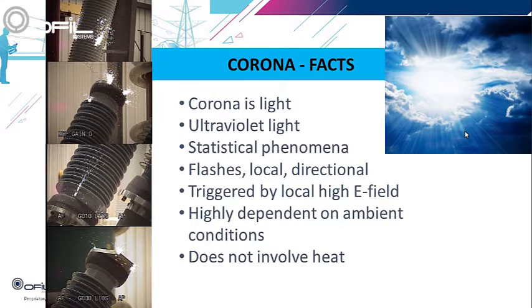Ultraviolet, being a short wavelength, has a high scattering coefficient. Scattering means fewer corona photons arrive at the detector. Scattering is inversely proportional to the fourth power of wavelength. As such, at UVC 240 to 280 nanometers — where corona cameras operate — the losses due to scattering are 20 times greater than in the visible range.